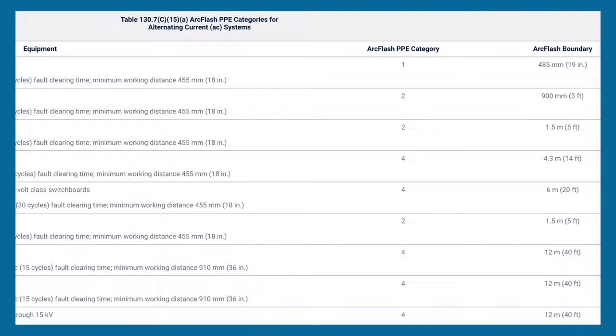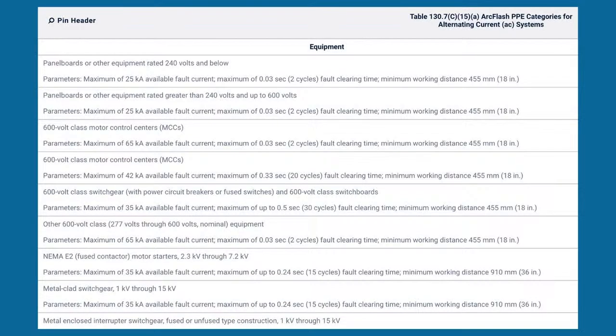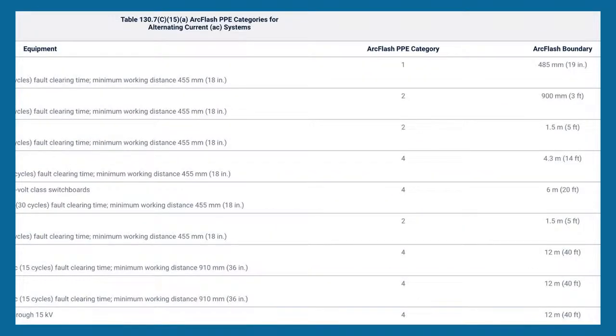Now, let's do something a little bit different, go down to the next one. I'm doing a 600 volt class motor control center, but look at the clearing time, 20 cycles, 0.33 seconds. Wow. Now, if that happens, you automatically went to hazard risk category 4, and now the arc flash boundary kicks out to 14 foot. 20 cycles, you're basically arc welding.